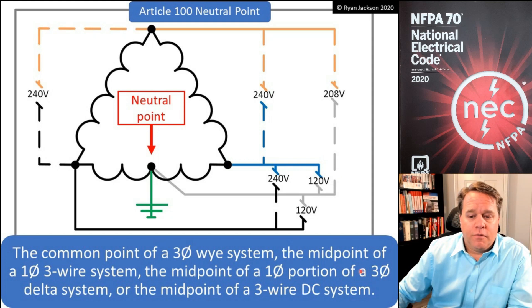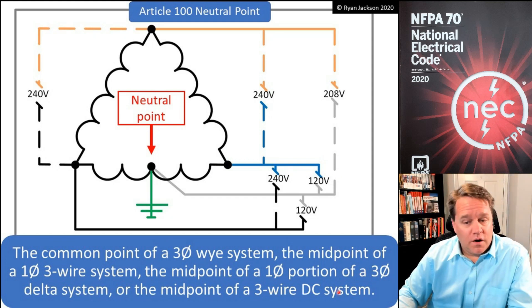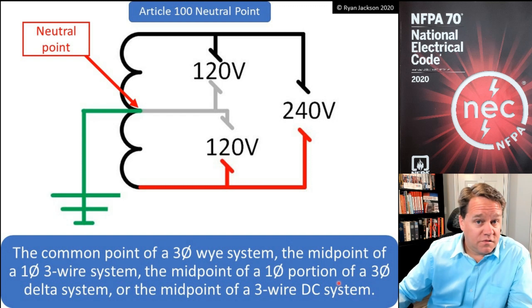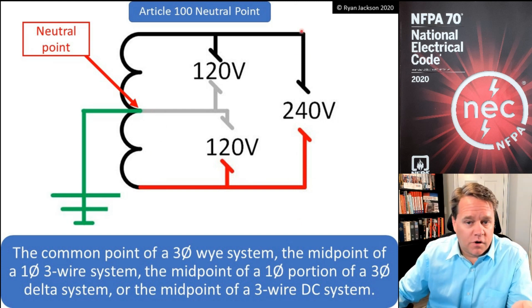We also have the midpoint of a single-phase three-wire system. On a single-phase system, it's 120 volts from one ungrounded conductor to the neutral point, 120 volts from the other ungrounded conductor to the neutral point, and 240 volts across the two phases. That midpoint would be our neutral point.